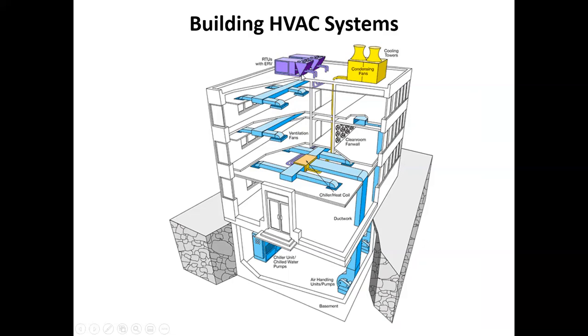What they do is, if you're going to use an ERV, you would pull all of that exhaust air, because when you're putting it in, you got to pull it out, and you run it through a heat exchanger. In the summer, that air coming out is say 72, 75 degrees. It's 95 outside. So you put that through an air-to-air heat exchanger and you pre-cool the fresh air with the leaving air. So instead of bringing in 95 degree air to your refrigeration system, maybe you can bring in 86 degree air. Well, that's a big deal, capacity-wise and energy-wise.